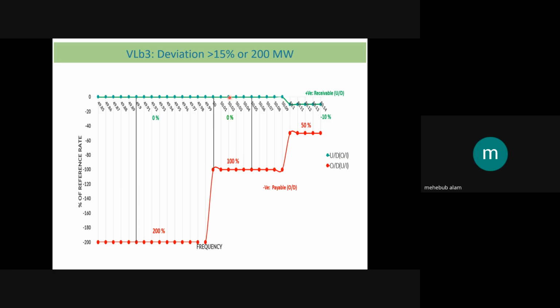Here the path will be a little bit different, meaning the slope will be different. Here the penalty will be 200% for the low frequency region, 49.85 to 49.99. The objective is a higher penalty for more deviation, greater than 15% or 200 megawatt. That means the DSM regulation says that we have to minimize the deviation. The lower the deviation, the better the grid stability. So we have to keep the deviation lower. If we deviate more than the schedule, then the penalty rate will be more. The penalty rate will be 200%.